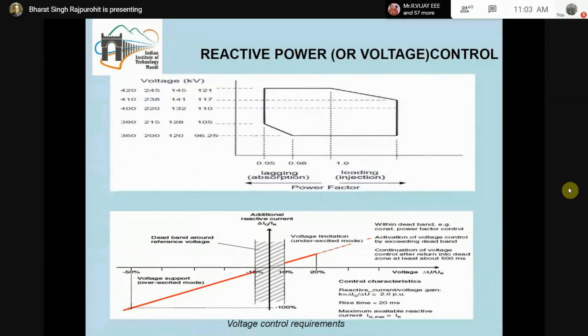Now please see this red line on the left hand side. The x-axis is the reduction in the voltage, that is, a voltage sag, where the voltage is reduced due to some fault. If the voltage is reduced to 50% of the rated value, then the reactive power requirement from the grid under this condition is 100%, or 1 per unit. The meaning is that if your machine is rated at, let us say, 5 megawatt or 5 MVA, and the voltage is reduced to 50%, then this 5 MVA wind turbine or wind energy conversion system should be injecting 5 MVAr to the grid. So this is a very strict grid code, but by utilizing the power electronic converter, it is possible to inject such an amount of reactive power.